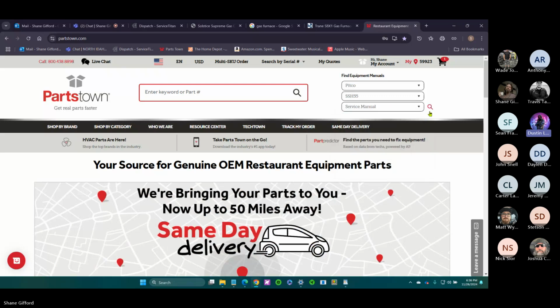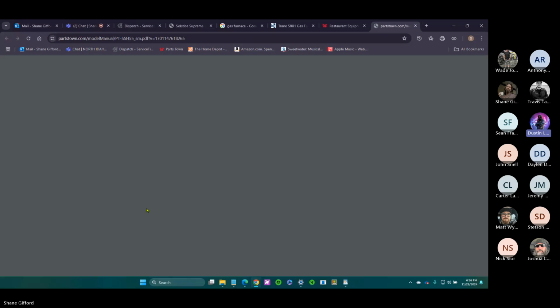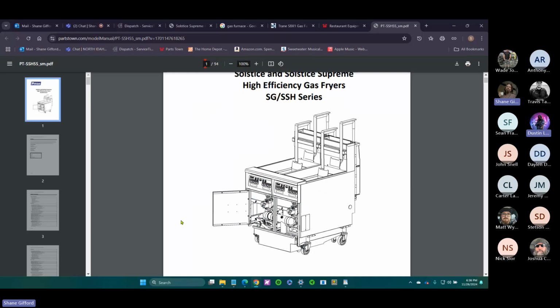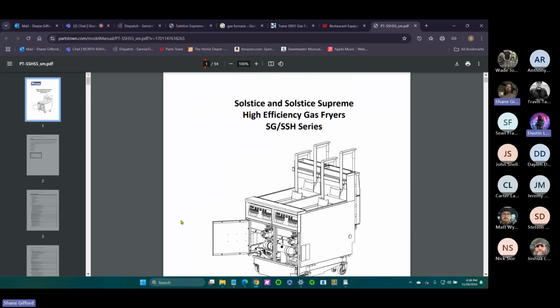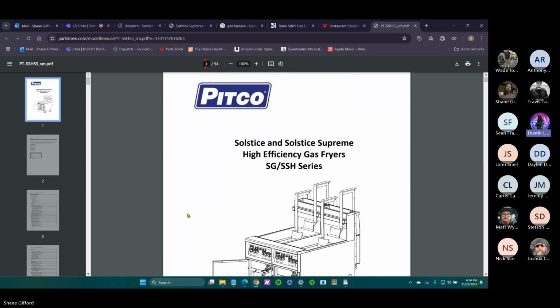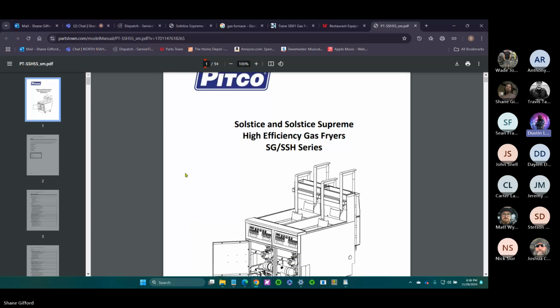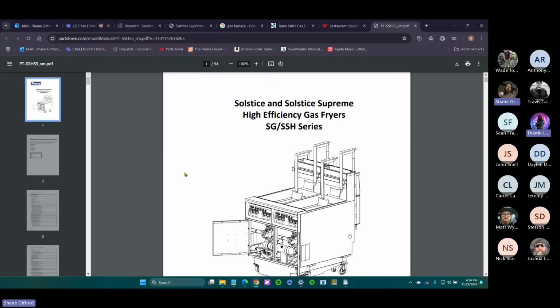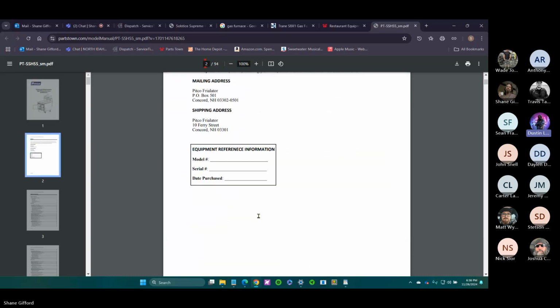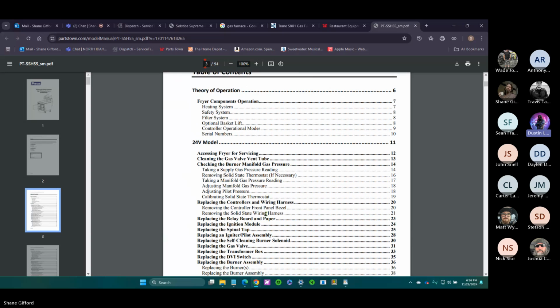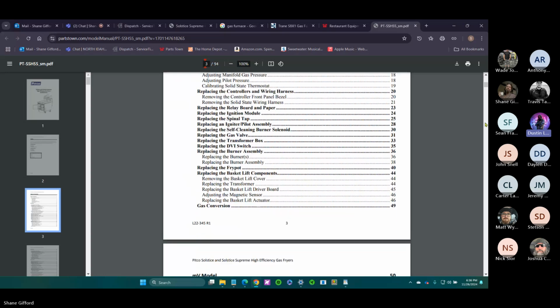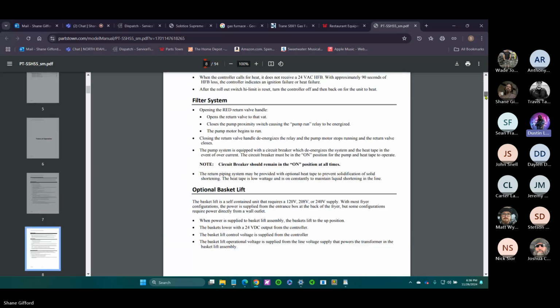And I've seen on the fryers too, the exhaust in the back gets all greased and plugged up, and you can't get rid of some of the heat, so they'll overheat that way too. And if anyone's ever worked on the weird ones at Freddy's, the turbo fryer or something like that? Those ones are weird. It's like the turbo air version of a fryer. They've got a burner chamber, like a big cylinder, and inside are metal baffles that distribute the heat evenly and make it go in a certain pattern to create an even heat pattern.